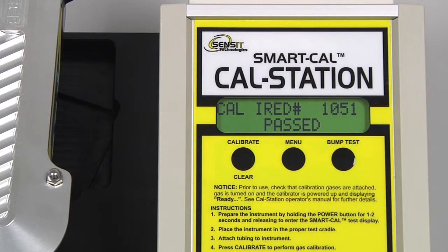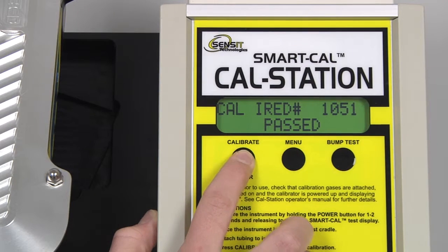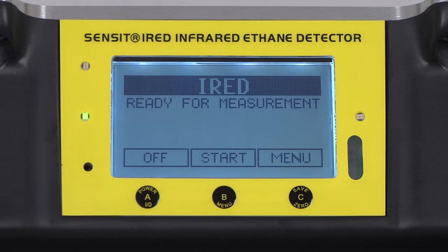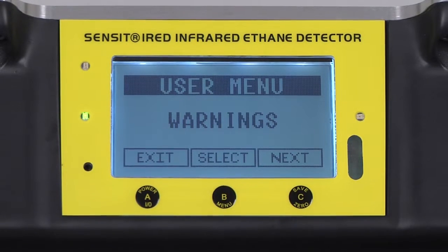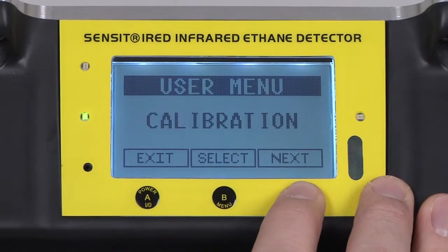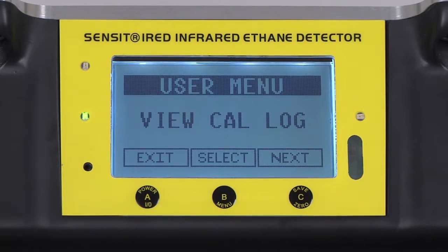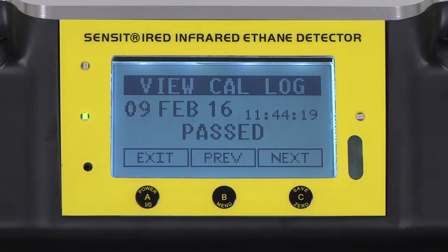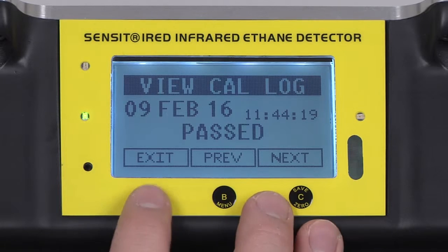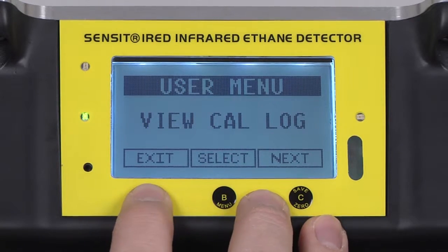The calibration was successful, indicated by the word passed, and we can now clear out of the calibration mode on the cal station by pressing and releasing the calibrate or clear button. To verify the calibration data of the IRED, enter into the menu by pressing and releasing the B button, and scroll by pressing and releasing the C button until View Cal Log appears. Select by pressing and releasing the B button, and the most recent calibration date will be displayed. Exit back to the working display by pressing and releasing the A button.